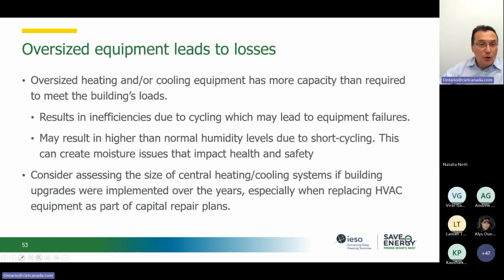We do get more losses because some of the losses are a function of the capacity of the system, some of the losses are a function of the load. But for the losses that are a function of the capacity of the system, we are going to lose this amount of energy no matter what the loads are. So it's kind of a standby type of losses.